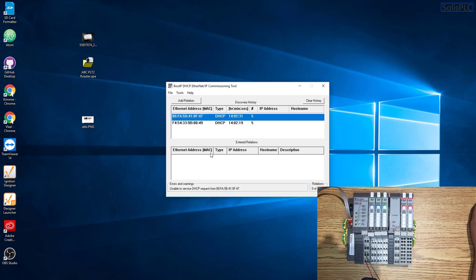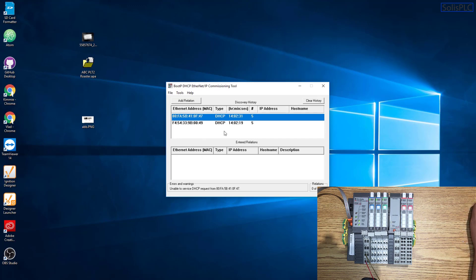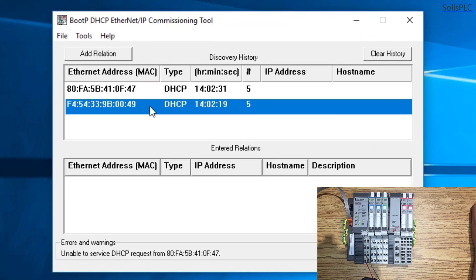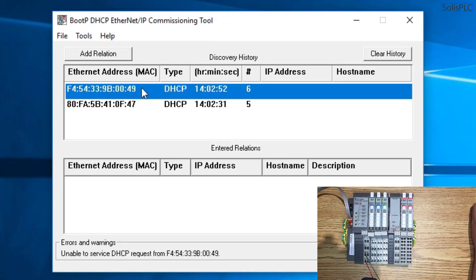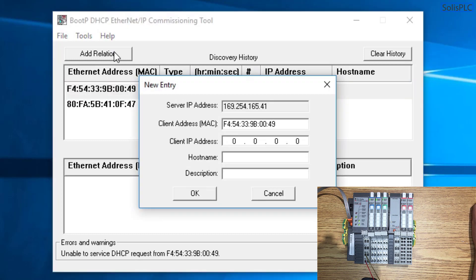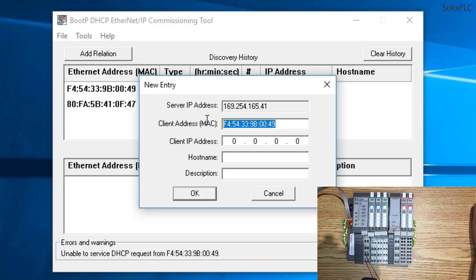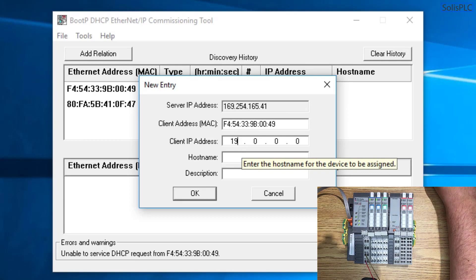The other thing that I recommend highly when you're working in a production environment is that you connect to these modules individually in order to avoid making mistakes by connecting all of them to, for example, a switch. And then you're just going to get a lot of different devices in here. So in any case, here I have the MAC address of the device as well as a MAC address of my Ethernet card. And I do need to select the proper MAC address in order to give it an IP address. So what I'm going to do is, first of all, I'm going to select it. I'm going to click on Add Relation. And here I'm going to once again double check that the MAC address is matching the device that I have in the field.